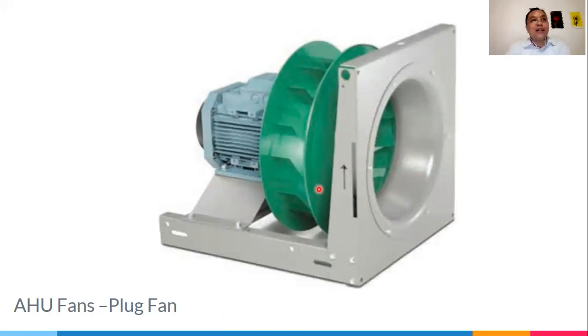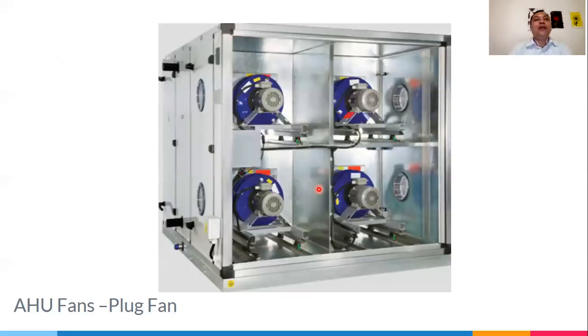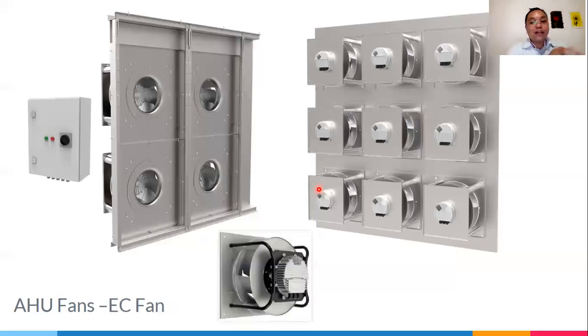It's cheaper because you no longer have the housing, and you'll be able to install multiple fans in one AHU, making your electrical consumption efficient. The third type is also a plug fan, but instead of using AC electrical current, you're using DC to remove the requirement of a variable speed drive.